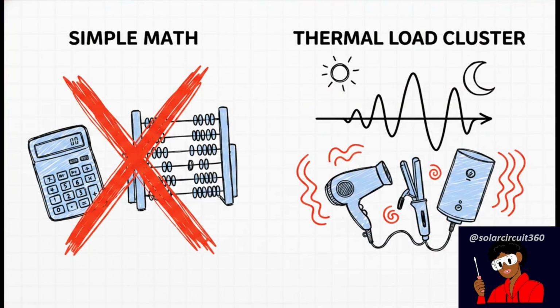A lot of installers mistakenly believe that designing a system is as simple as opening up a spreadsheet and just adding up the nameplate wattages of hair dryers, standing dryers, water heaters, and so on. But here is the raw truth. Salons are thermal load cluster systems. They are absolutely not a simple watt sum. If you treat the electrical demand of a busy salon like a basic 1 watt plus 1 watt equals 2 watts math problem, your inverter is going to cook faster than a bad perm.